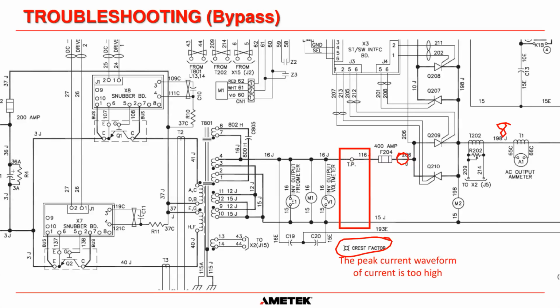And remember, I said for a 10 kVA system, it should be 83.3 amps RMS. So if you measured 83.3 amps RMS, you think, well, okay, the system should be okay. But if you put your meter on peak to peak and you saw a huge peak, let's say 300 amps peak load currents, then that's too much for our IGBTs to handle and will probably damage them. So our system will transfer to bypass if it sees high peak current, and that will give you the crest factor alarm on the back of the board.